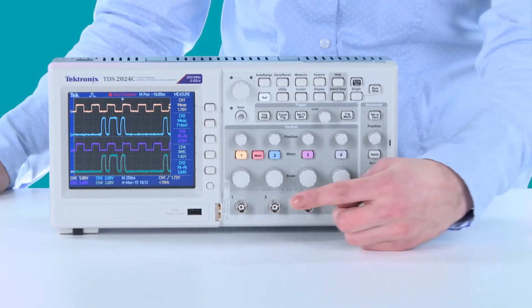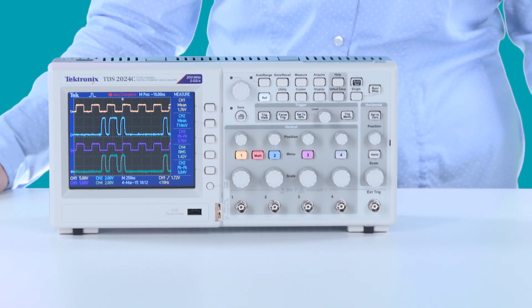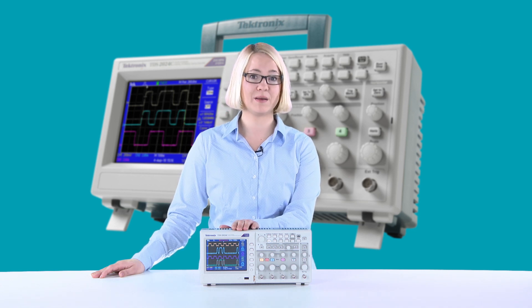TDS2024C comes with four analog input channels and has 200 MHz bandwidth, and you have on all four channels 2 Giga samples per second sample rate available.